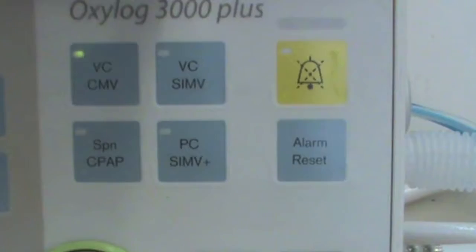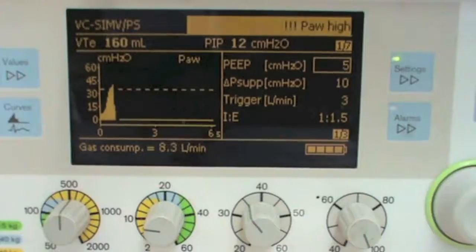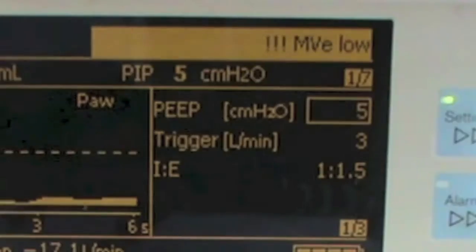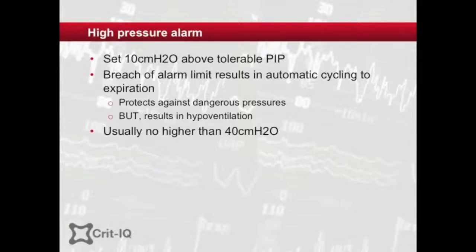This results in a truncated inspiration, and as such, much lower volumes are delivered than have been set. As a result, the lung is protected from the high pressures, but the consequence of this is that the patient may be dangerously underventilated. In practice, peak pressure alarms are set to around 35 to 40 centimetres of water.